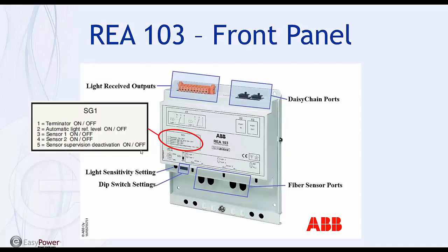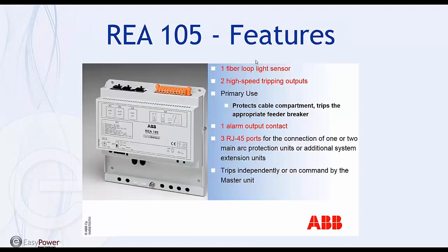So the default is deactivation off. Basically that means it's being supervised. Unless you don't want to supervise it, then you would turn that switch on. If you have radial sensing, then you can't supervise. You have to have a loop to supervise. Now let's go to the REA 105 features.